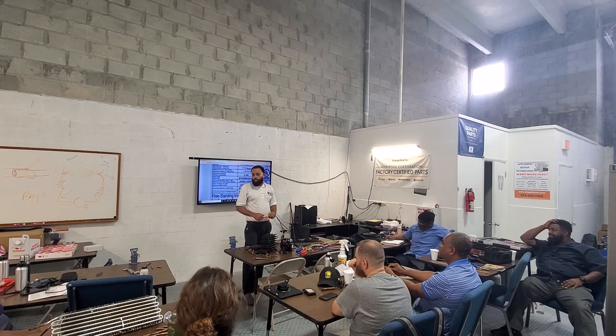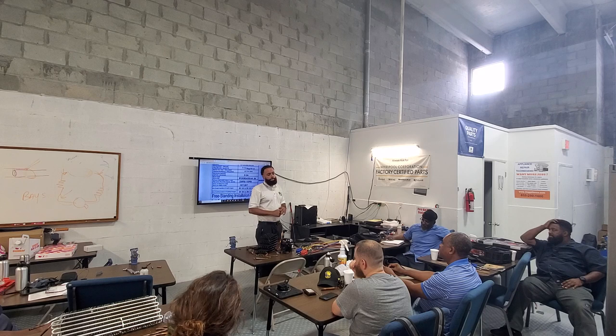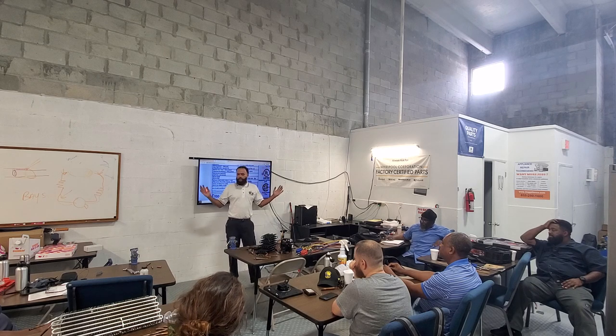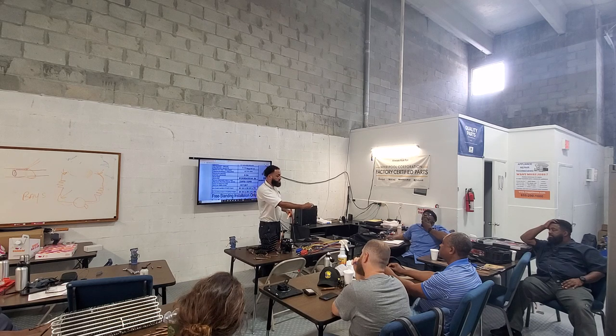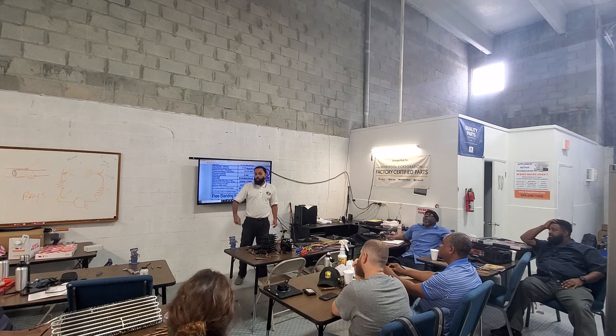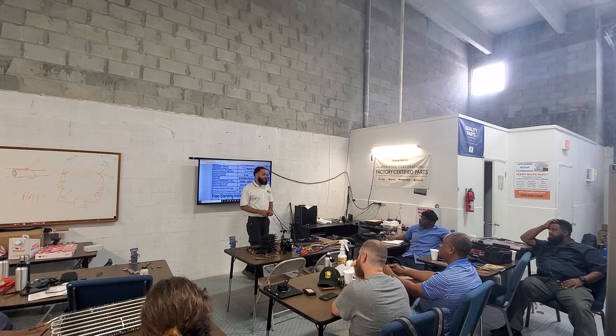What do we do with the nitrogen in the system? No problem. EPA ain't gonna mess with us, right? We address that. We look at it with an inspection mirror. We put how much again, Gene? 103. And we don't see that bubble this time.